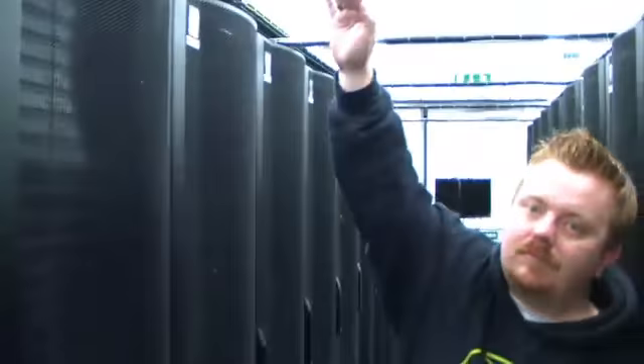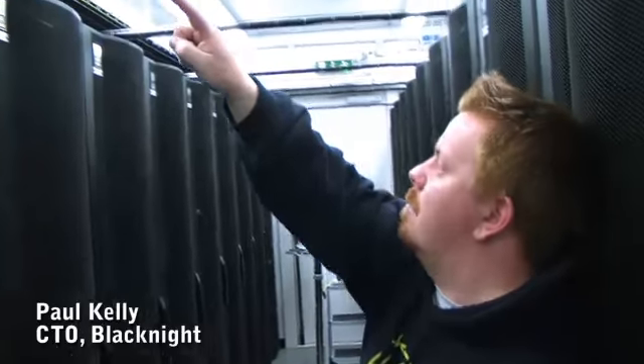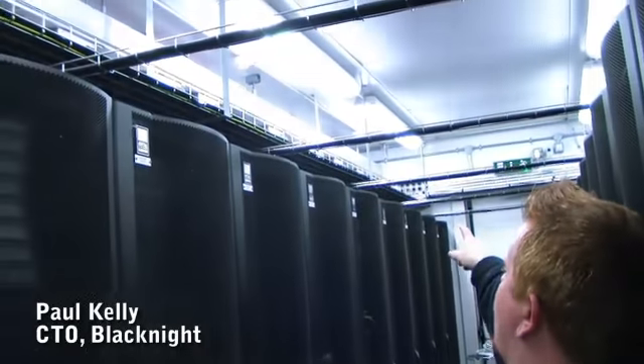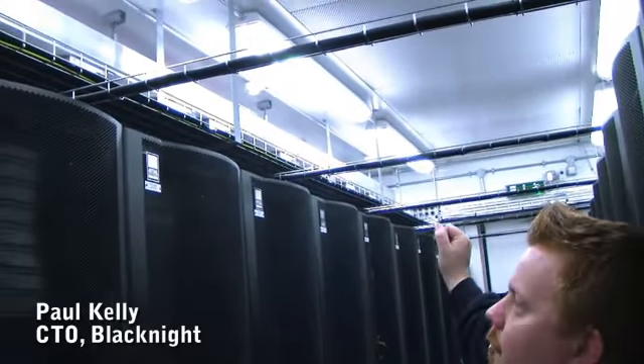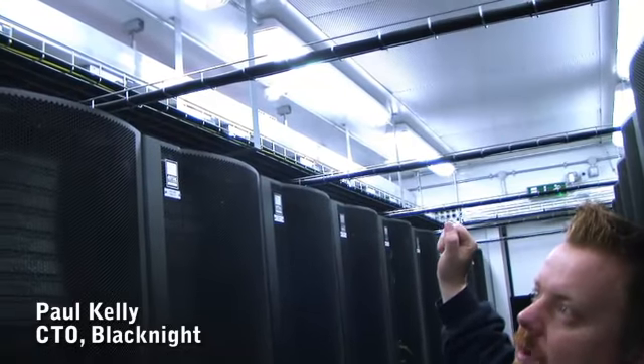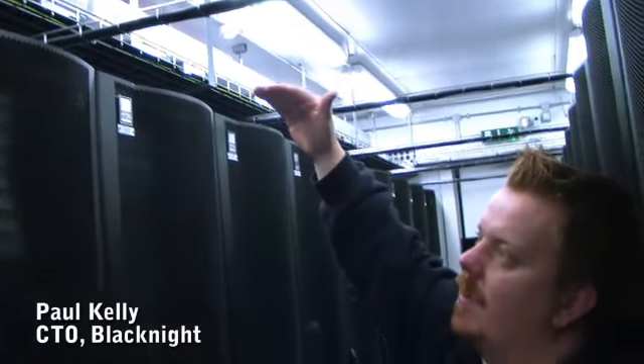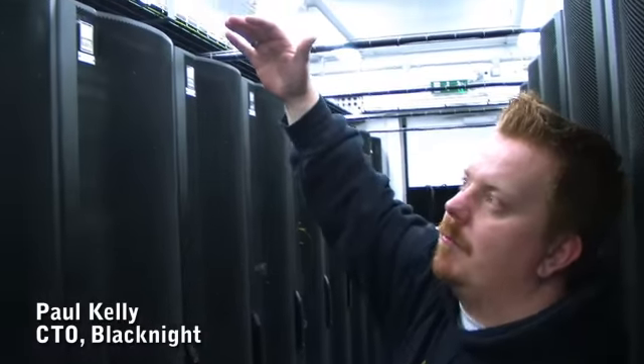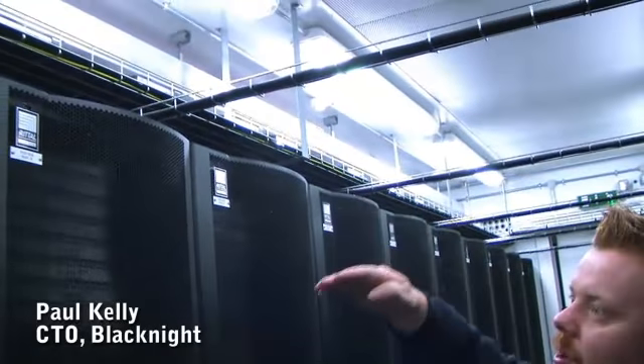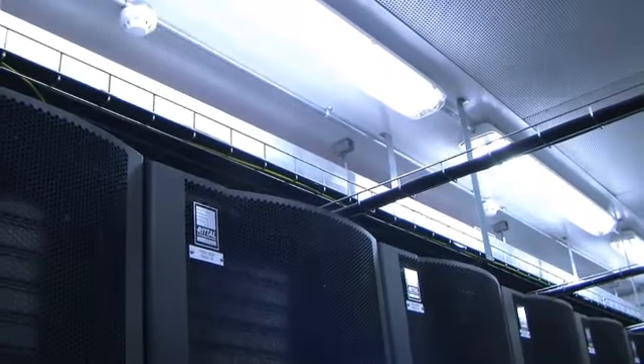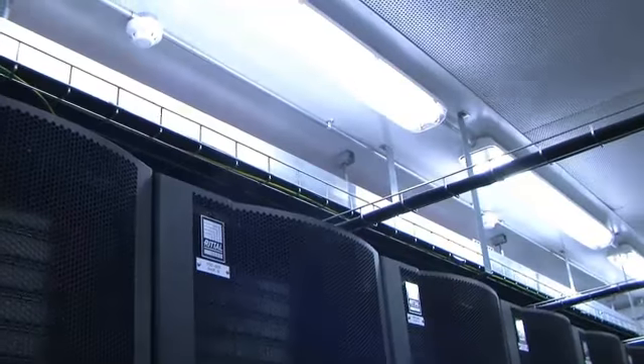Everything's upside down. Right. Power is overhead. So you see the metal busbar that runs the length of the building. That's a 250 amp, 3-phase busbar that has 32 amp breakers all the way across for each rack, and there's one on either side. A and B feeds. Each rack is fed with both. And we'll do a quick look at the back in a minute, and we'll get a look at the PDUs, how they're wired.